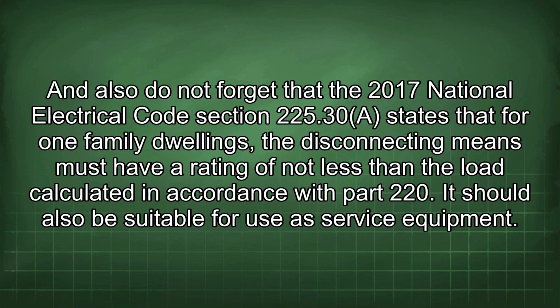And also do not forget that the 2017 National Electrical Code Section 225.30 states that for one-family dwellings, the disconnecting means must have a rating of not less than the load calculated in accordance with Part 220. It should also be suitable for use as service equipment.